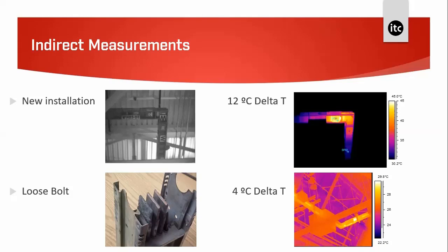So luckily, we have daylight pictures that show how these bars are connected at the unions. And I think it really does help to understand that if we get a high resistance on those connections, we see it quite clearly.